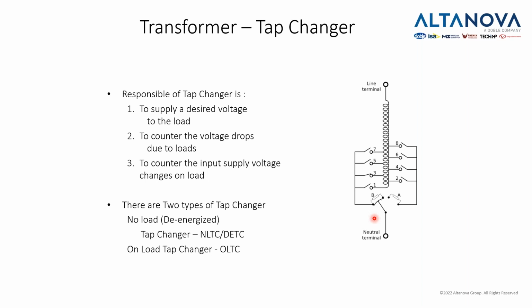There are two types of tap changers, the de-energized tap changer and the on-load tap changer. The de-energized tap changer you will mostly find on the distribution transformer, while the on-load tap changer is more frequent on the transmission transformers. And also, it's not a rule, but very often you will find the tap changer on the primary side of the transformer if we talk about step down, because it is a lower current on the primary side and it's easier to handle the change of a lower current.